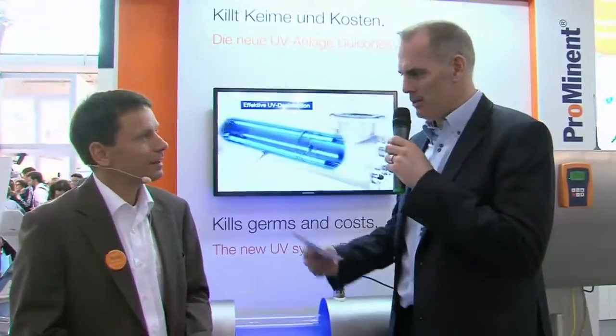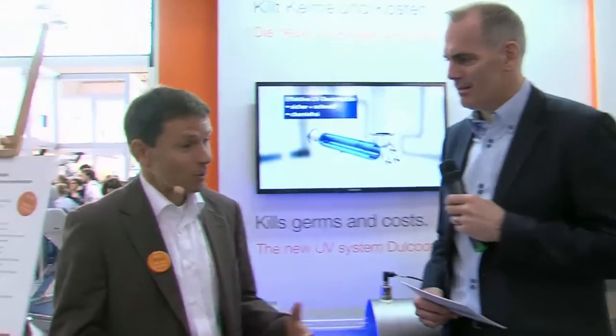You just spoke about the lamps — the Varia Flux lamps, which you invented for the Dulcodes LP. What is so special about them? In order to be as efficient as possible, we wanted to dim the lamp — to change the power of the lamp to adapt it exactly to the flow rate the customer has. This sounded easy, but in reality it is not. The lamp temperature is affected by the water temperature because the heat from the lamp is transferred into the water. The colder the water, the colder the lamp. If a lamp gets too cold, the UV intensity becomes unstable, going up and down, and you don't want this because if the UV intensity is not stable, you cannot have a safe disinfection.